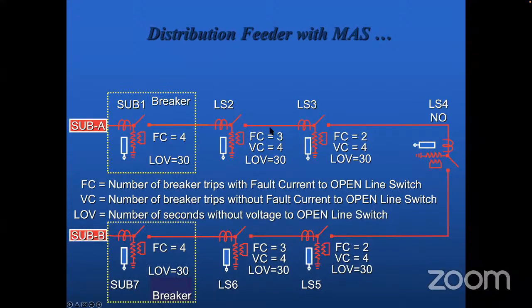Remember, these switches cannot be opened or closed while the fault is present. These are not breakers. Only a breaker has the capability to open during the fault. Now, the number of breaker trips without fault current to open the line switch: you are seeing no voltage, but you are not seeing any fault current. That's the count of VC. LOV is the number of seconds without voltage to open the line. You can design this however you like. This is how they thought their system would look. So after 30 seconds without voltage, it will open up. Remember, these switches cannot interrupt fault current; they don't have the capability.